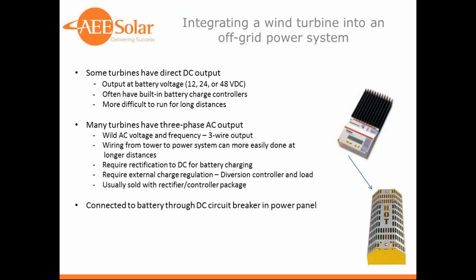So typically they require external charge regulation, meaning a diversion controller such as the Morningstar TriStar pictured here, and a load such as this DC heater load pictured here. You could also use an AC dump load if you have a relay that turns an AC load on, run by the inverter. One way or another, you need to be able to dump or divert that energy once the battery is full.